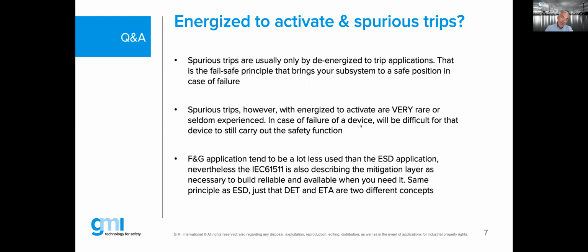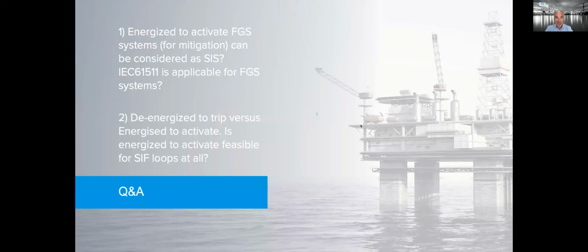So, last bullet, fire and gas applications tend to be used a lot less. We all know that. Otherwise, you would live in a very strange plant, or a very dangerous plant, if you used your fire and gas systems as frequently as your shutdown systems. That means the mitigation layers tend to be used a lot less. It doesn't mean you have to build them a lot less reliable, because when you need them, you will need to be trusting that you can use them. That's why reliability, or your SIL, is also becoming a part of the 61511 as per edition number 2. Okay, Andrea.